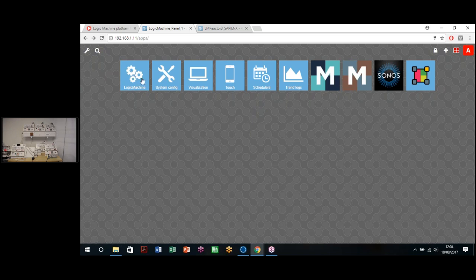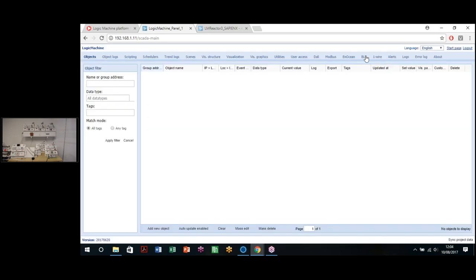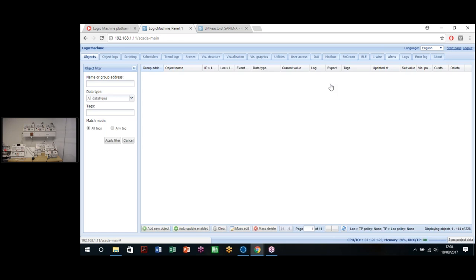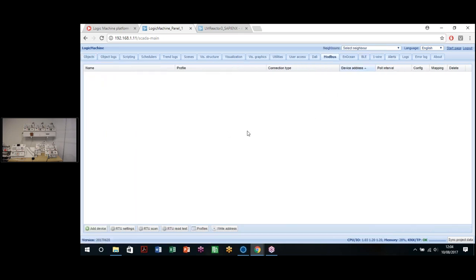For Modbus configuration, in the Logic Machine screen, we can see that we have a specific Modbus tab. When we click in the Modbus tab, we can see, in this case, we don't have any object, any interface, any Modbus device connected. So the first thing we need to do is create a Modbus profile, so the Logic Machine knows which address, which object of the Modbus device, we are referring to.